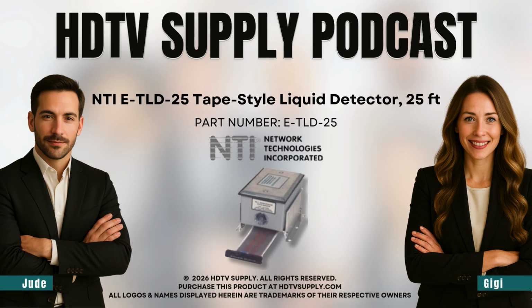We're not talking about waiting for some big puddle to form. This thing can register a minimum puddle diameter of just 0.125 inches, that's 3 millimeters. It's tiny. Why is that so important? That level of precision seems almost like overkill. Well, think about it. In a high-density server room, you want to catch a pinhole leak, a single drop, before it ever has a chance to pool or spread, before it starts wicking up into cables and causing real damage. If you wait for a standard sensor to get submerged, you've already lost critical time.